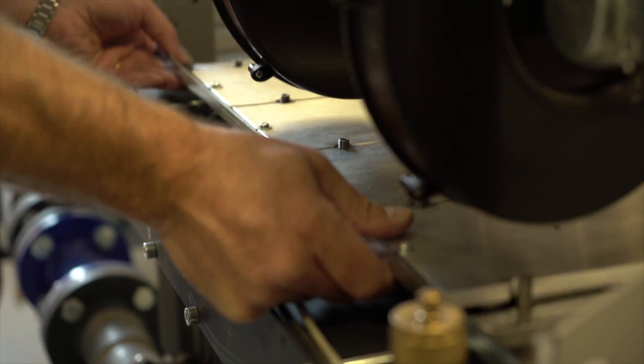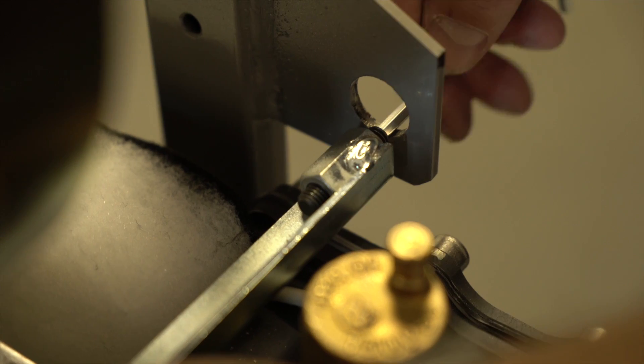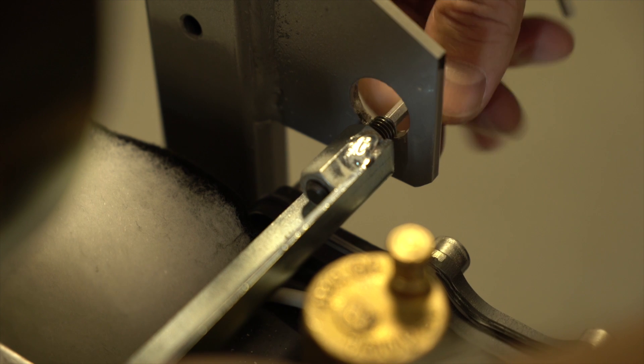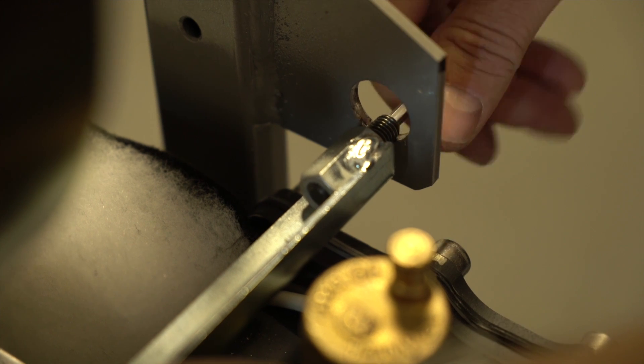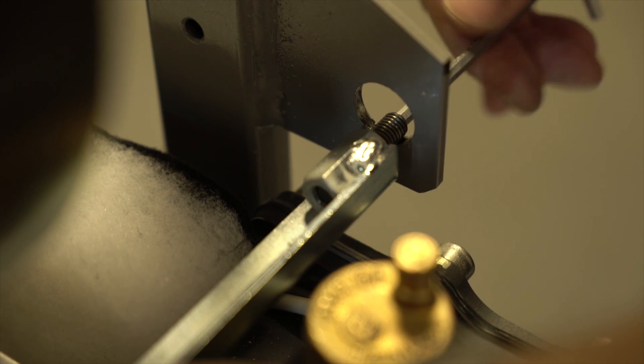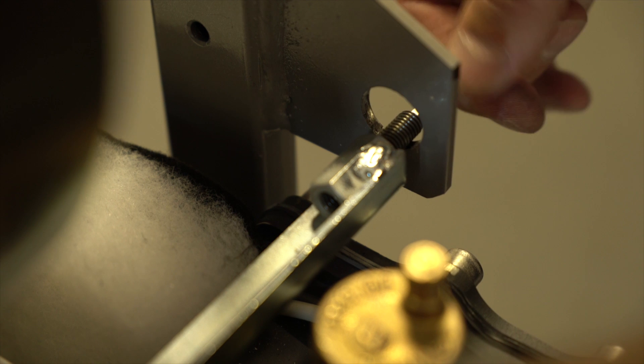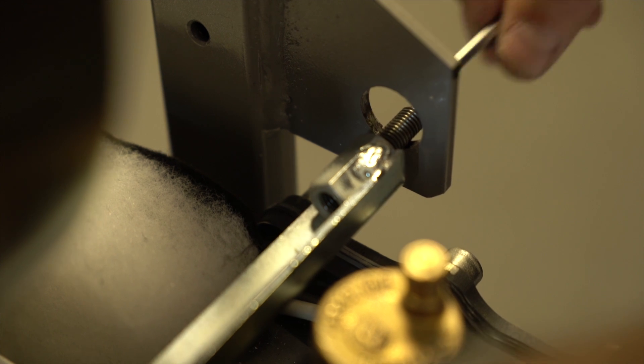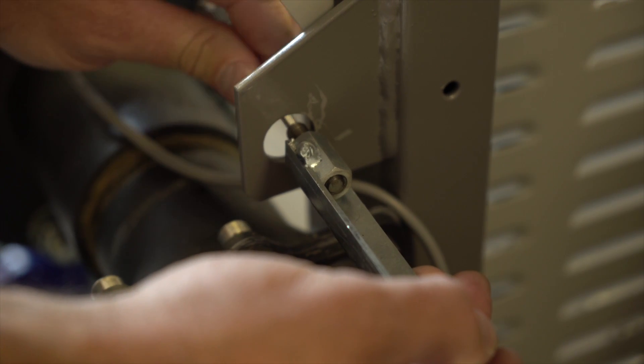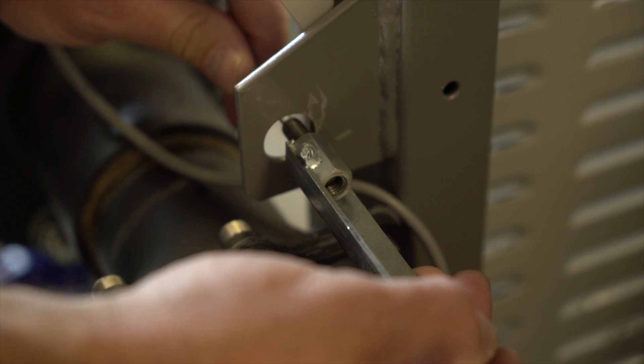Standing at the back of the boiler, lift the burner block to align grub screws with bracket holes. Using a 4mm hex key, wind the grub screw anti-clockwise until it engages with the bracket. Repeat for other side. This then acts as the hinge mechanism.